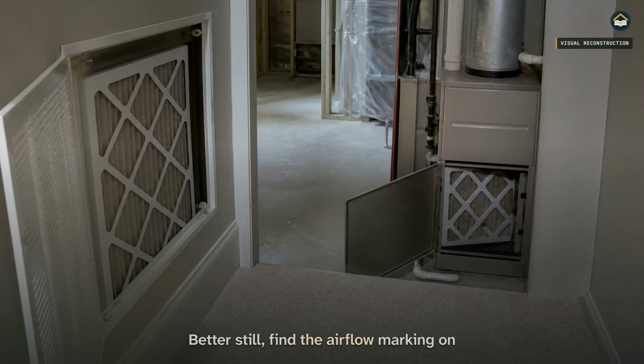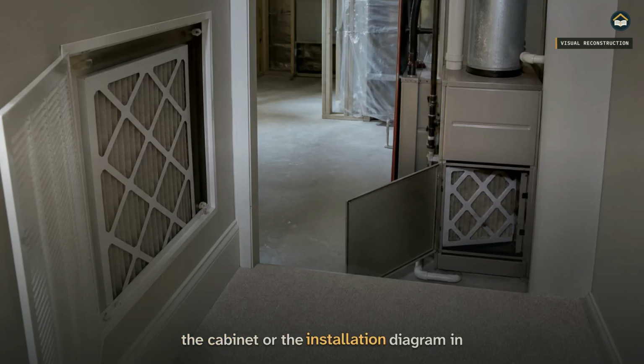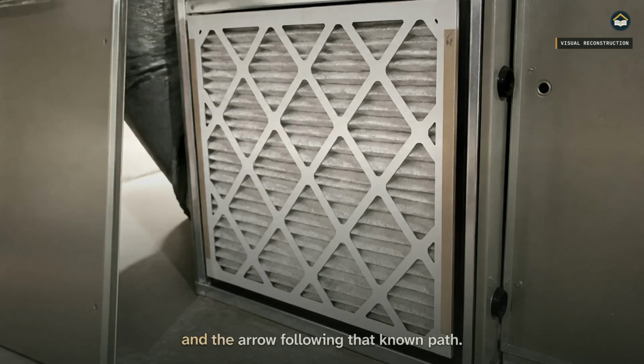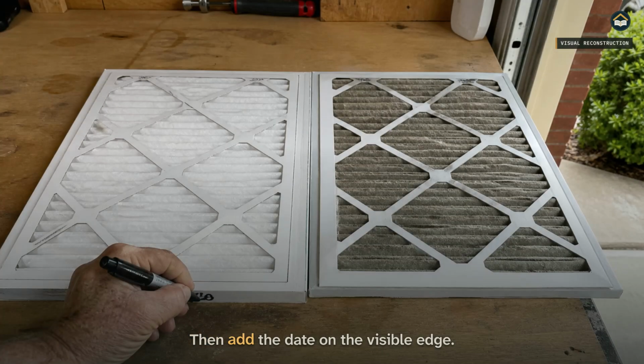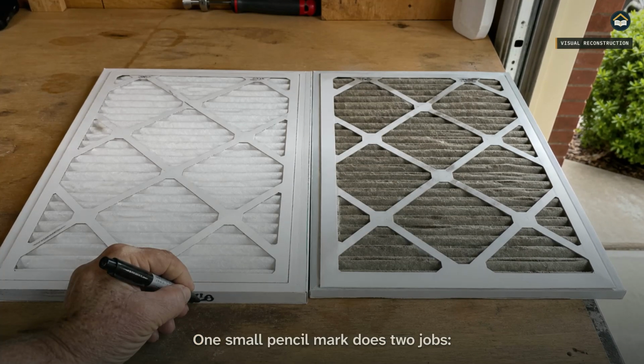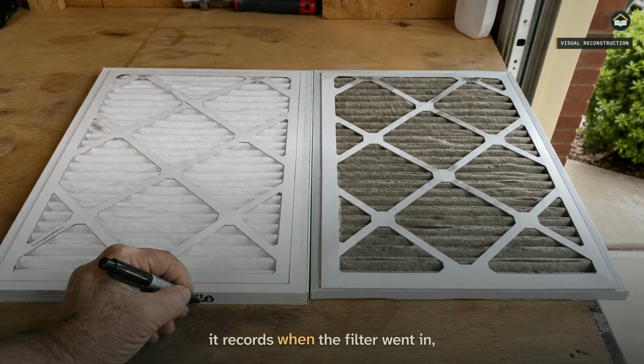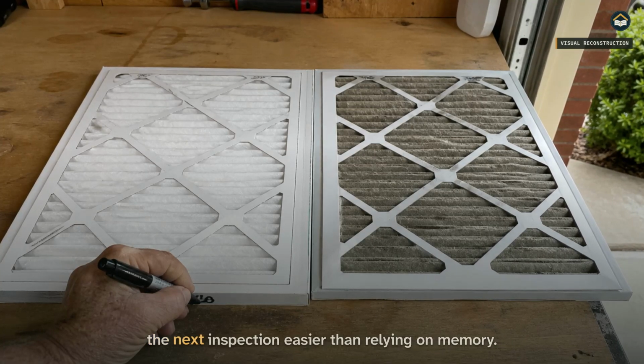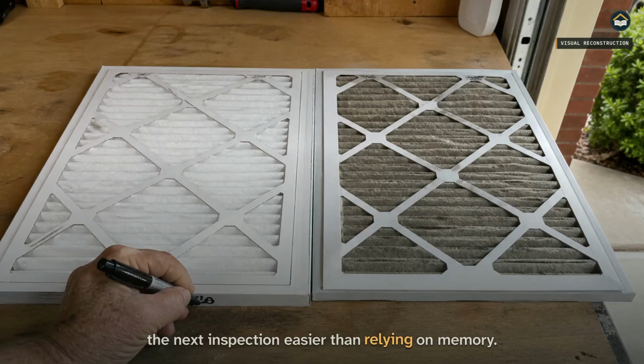Better still, find the airflow marking on the cabinet or the installation diagram in the manual. Install the filter with the frame square and the arrow following that known path. Then add the date on the visible edge. One small pencil mark does 2 jobs. It records when the filter went in, and it makes the next inspection easier than relying on memory.